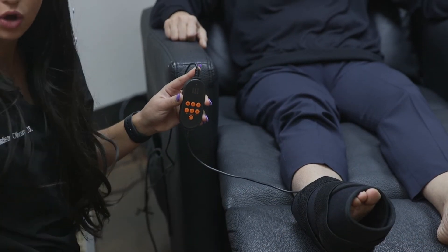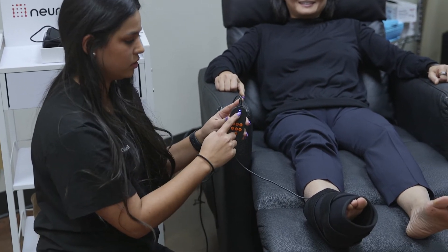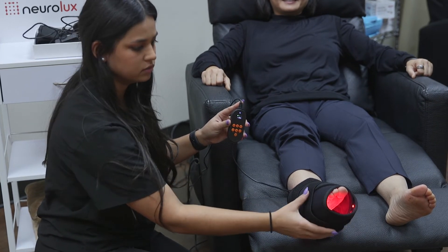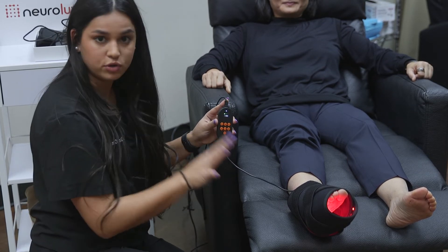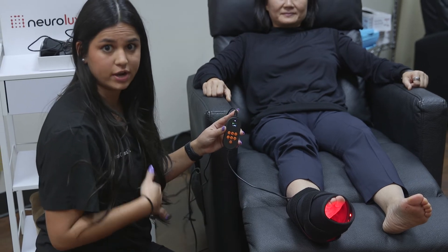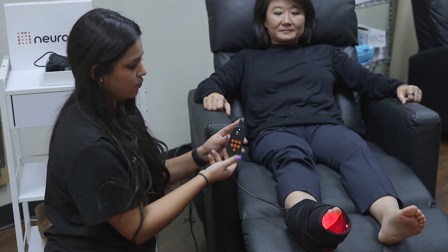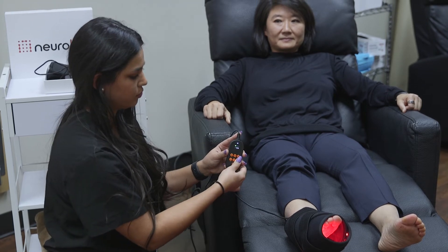To turn the NeuroLux light on, press the power button. When the light is on, a small indicator light will appear on top of your remote. Then press R, which stands for red light — you'll notice red lights turn on inside the shell. You can leave it on constant, but for most patients who are time-constrained, use the timer: press Roman numeral I for 10 minutes, II for 20 minutes, or III for 30 minutes.